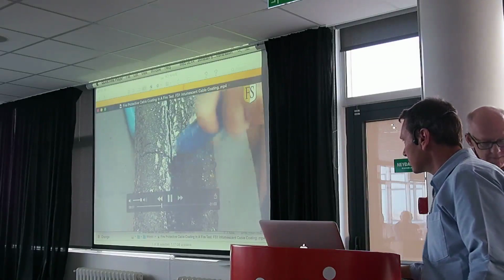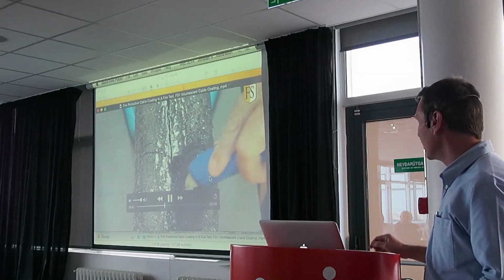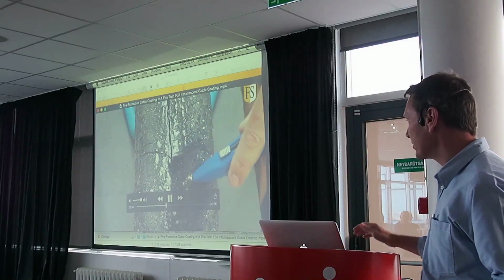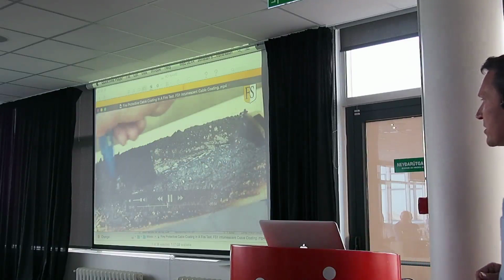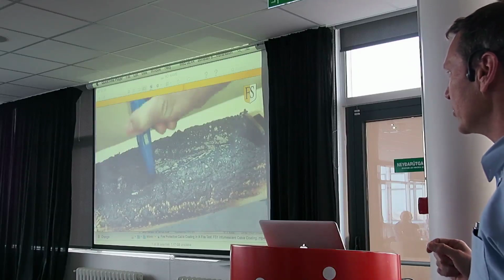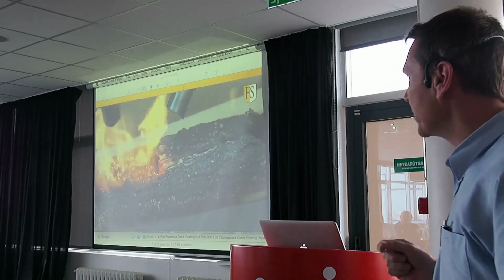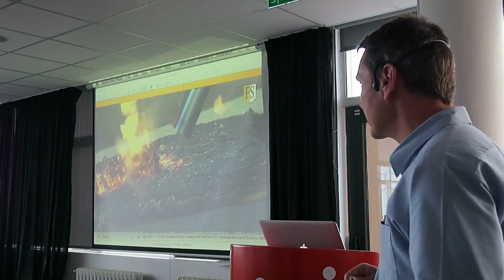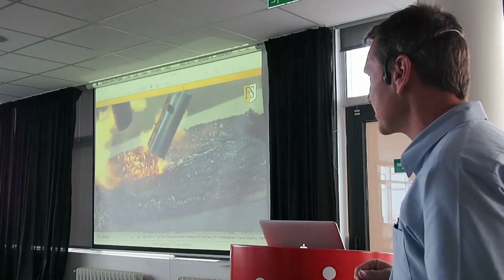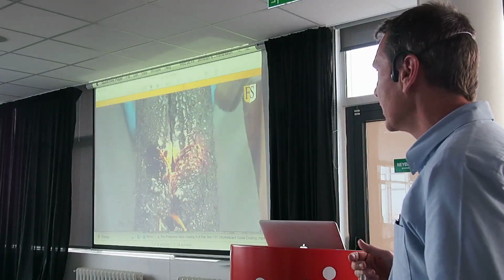Probably was just explain it rather than dealing with the technology. Okay. What this is actually showing, sorry, they're fixing their cable. What this is actually showing is one of our products. This is an 1100 degree burner, and it expands. It's an intumescent coating. What happens under fire? It fully expands up to 100 times its thickness to insulate and protect the electrical cable.